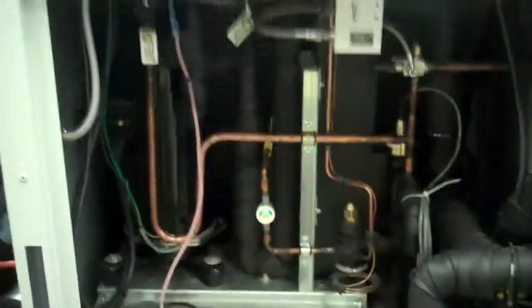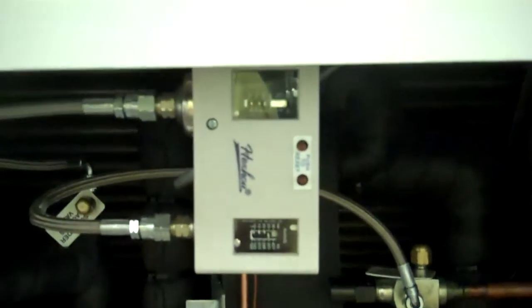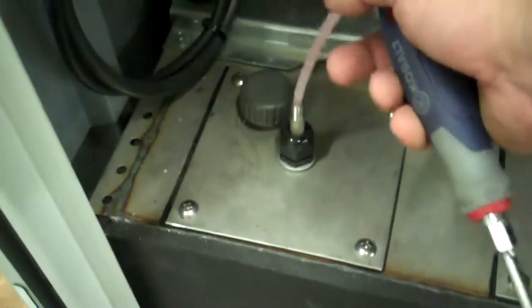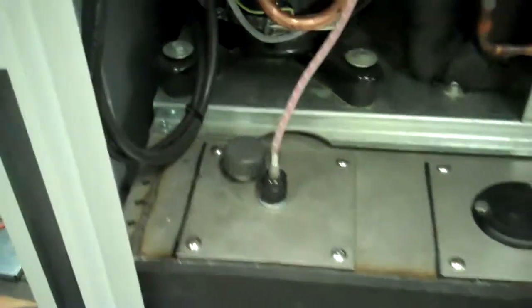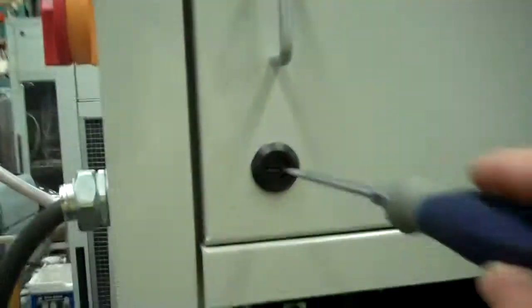While we're doing that, we'll just talk about a few other things. That's our low pressure and high pressure switch integrated back into the controller. This is our sight glass. These use R407C, and that's what you want to see is a nice lime green sight glass to indicate that it's dry. Here is the fill for our tank. This one does actually have a level switch built in as a safety, so if the level gets too low, in addition to the visual that you see in the sight glass here, it will shut off the system.